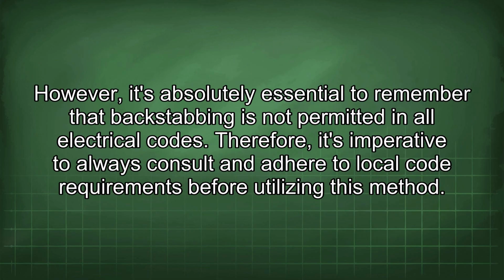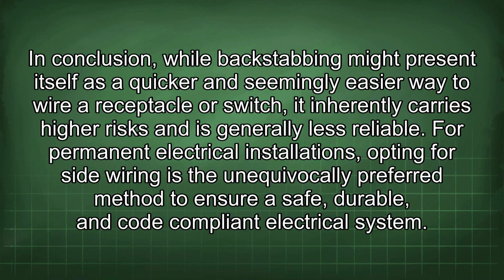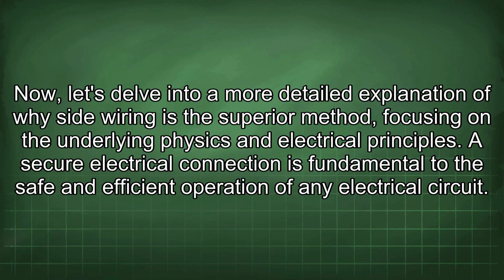However, it's absolutely essential to remember that backstabbing is not permitted in all electrical codes. Therefore, it's imperative to always consult and adhere to local code requirements before utilizing this method. In conclusion, while backstabbing might present itself as a quicker and seemingly easier way to wire a receptacle or switch, it inherently carries higher risks and is generally less reliable. For permanent electrical installations, opting for side wiring is the unequivocally preferred method to ensure a safe, durable, and code-compliant electrical system.